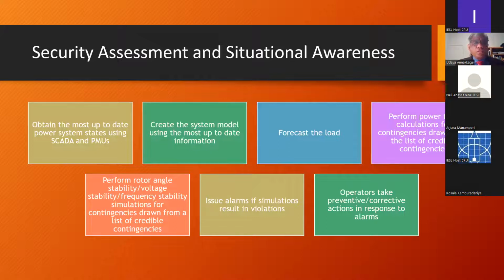The difference between synchrophasor measurements and typical SCADA measurements, SCADA stands for supervisory control and data acquisition, is that synchrophasors are synchronized. It doesn't matter whether you take the measurement at Anuradhapura power station or Anuradhapura substation or Kotmale substation. You take the measurements, sample them, add a timestamp from GPS, and transmit it to the system control center. So when the system control center receives this data, it doesn't come in a synchronized manner because there are delays of transmission and calculations and so on.